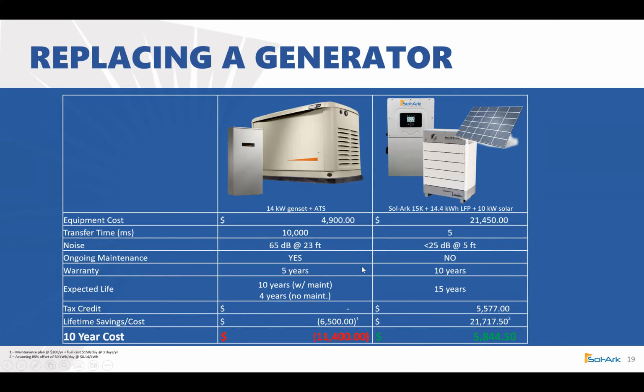Warranty periods are going to be a lot shorter on a generator. Our warranty goes up to 10 years on solar, and the expected lifespan of the Sol-Ark is up to 15 years. And if you don't even maintain your generator, it's going to last 4 years if you continually run it. You're not going to get a tax credit for a generator either. Right now, this is calculated at the 26% tax credit. Starting next year, we're going to get a retroactive 30% tax credit, and then ongoing for the next 10 years. So for your lifetime savings, at about a 10-year cost, we'll be saving you money versus losing money to ongoing maintenance on a generator.